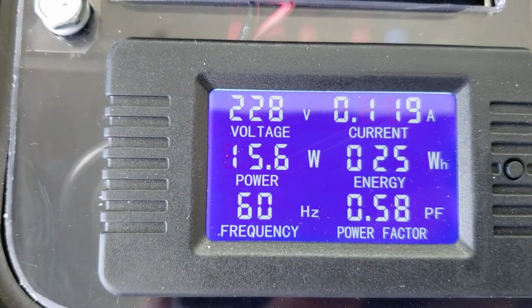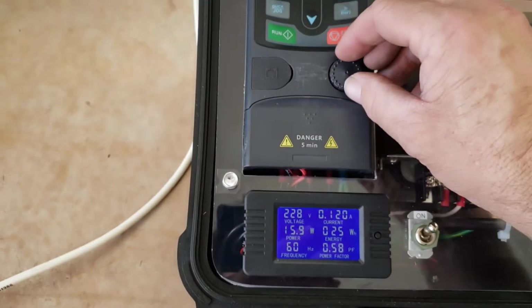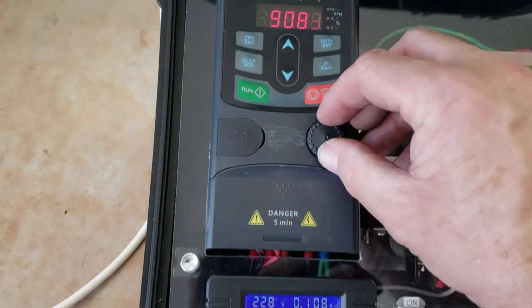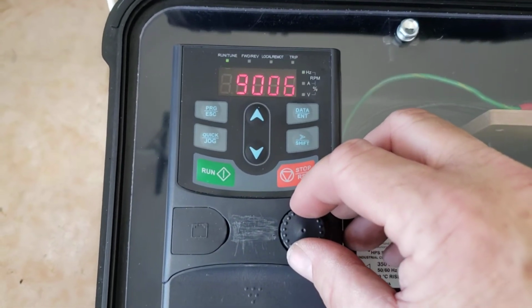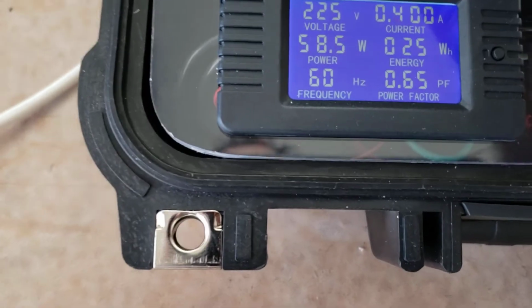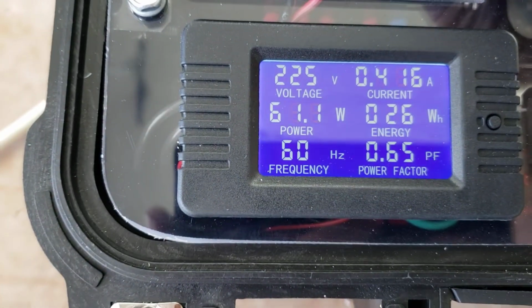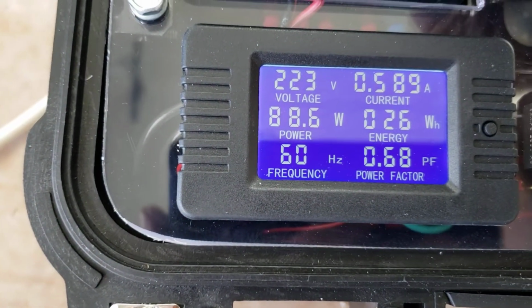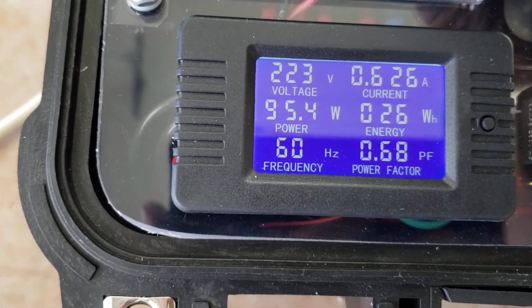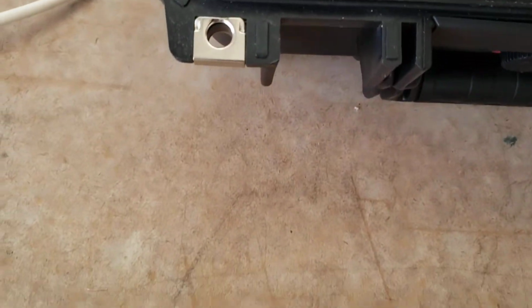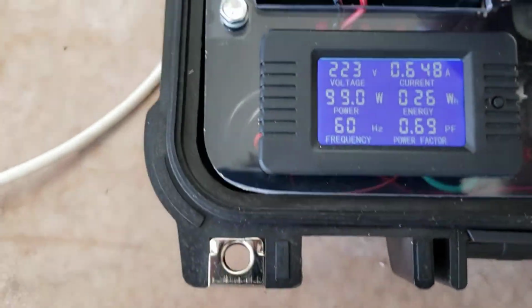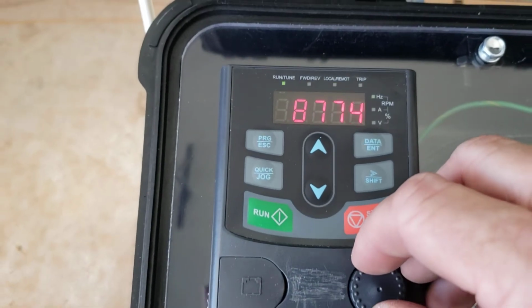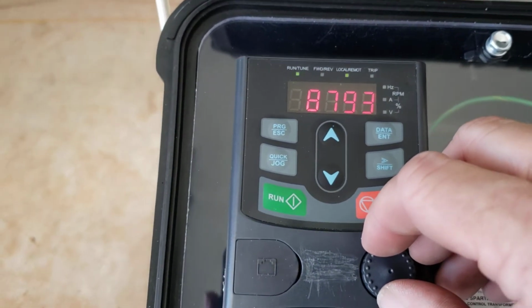Minimum is roughly 15-20 watts. As you turn up the potentiometer, you'll see the frequency begin to drop. Wattage should go up. You're watching for the wattage to continue to go up. On a good cell, it'll go up to about 400 watts. On a bad cell, that wattage will not go up, and the frequency will not go linearly down as you go up in power. You're also listening for any chattering or arcing in the cells.